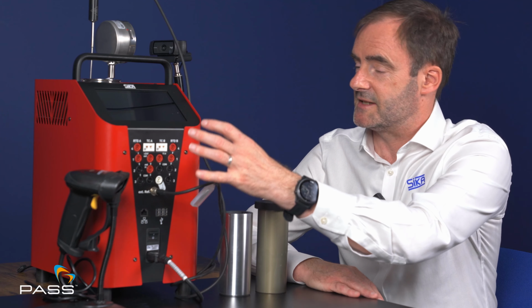So with all the functionality within the front screen, we can offer customers from PT100s all the way up to amplified milliamp outputs, K-types. There's a wide variety of different temperature sensors, but there's also a wide range of temperature sensor shapes. Not only are they just straightforward probes which go into a process, but we have weird shapes and sizes, and that's where you'd use something like a bath. So you can actually drop the sensor into the liquid bath, and then we can calibrate a weird kind of shape of a sensor as well if you needed to.